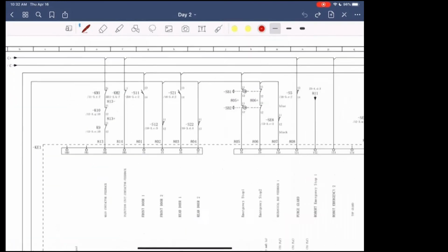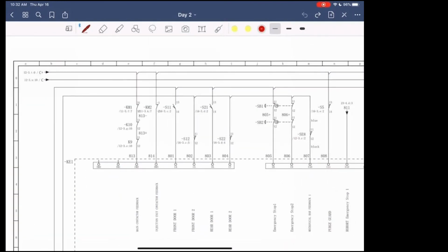All right. Again, keep in mind when you're looking at these things, for example, the front door. Well, it's a normally open circuit. So why am I getting a signal in 801? Well, when you close the front door, this is going to close. And when you close the front door, this is going to stay closed. So it knows to check to make sure that it has the signal at all times. So when you open the door, this one's going to open, and this is going to open. So it kind of does the opposite of what you're actually thinking of. In order to get a signal to any one of these connectors, you obviously have to have all the switches closed. So in order to have all the switches closed, they have to change status.